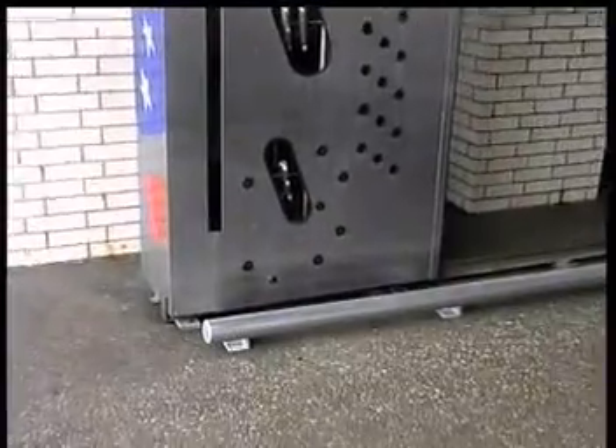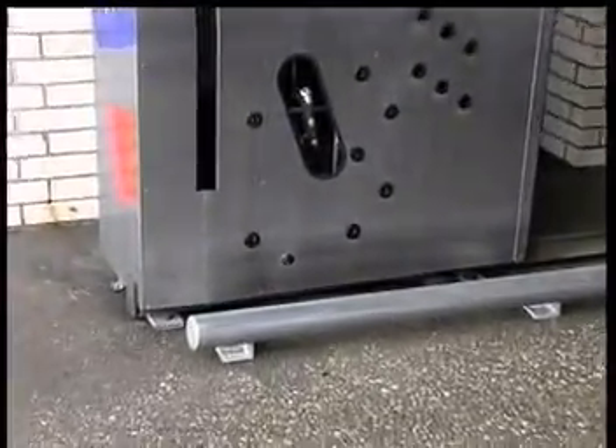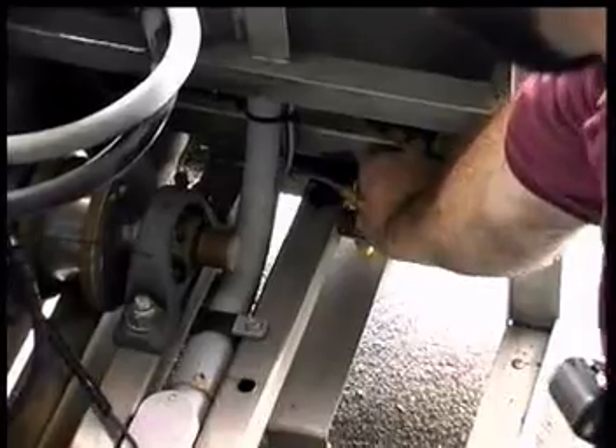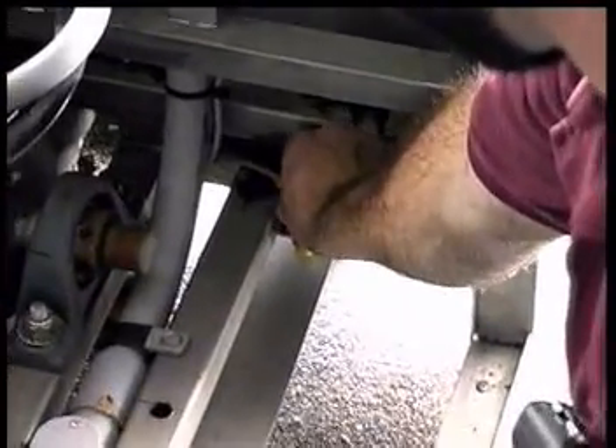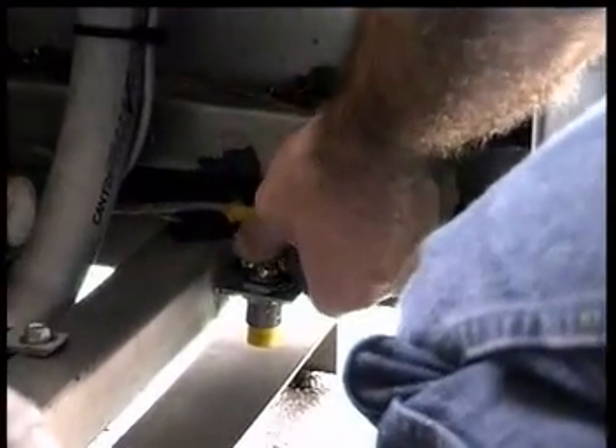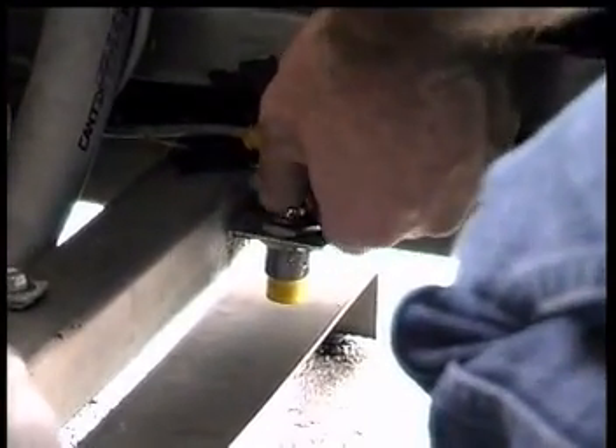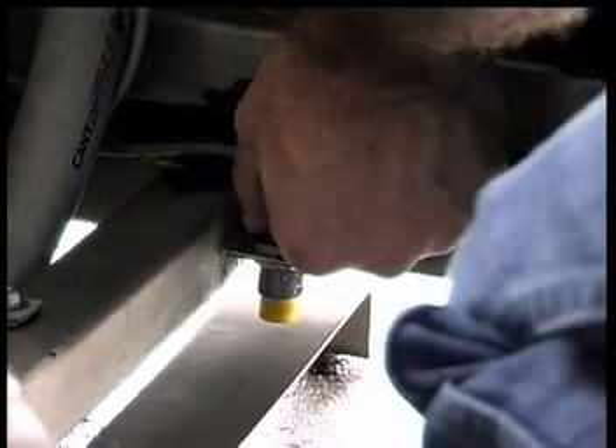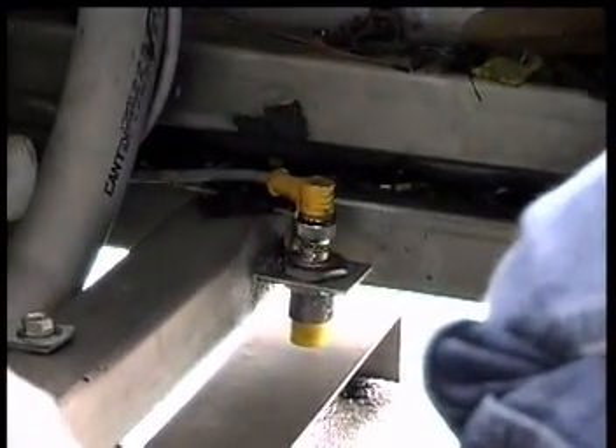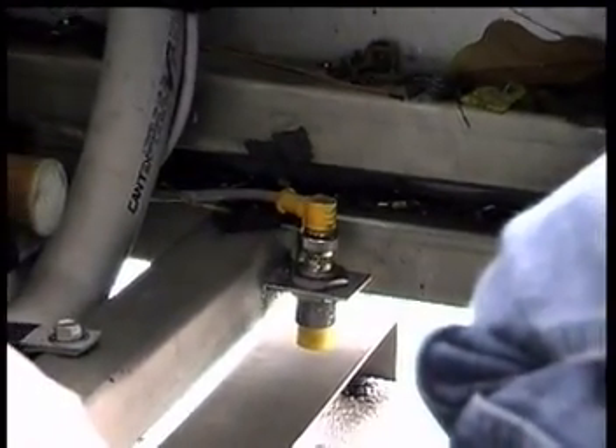If the gantry is stuck at the entrance or exit end of the tracks, check the corresponding proximity switch. Refer to the prox section for proper operation and troubleshooting. If a fault is present and the unit is still operating, check both end of track and home position proximity switch adjustment. Also check for loose connections or worn cables.